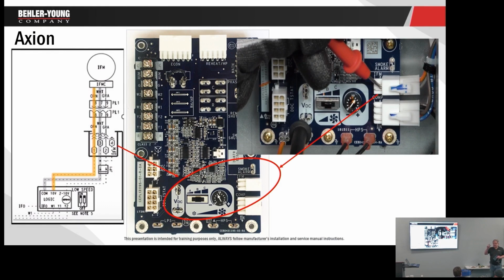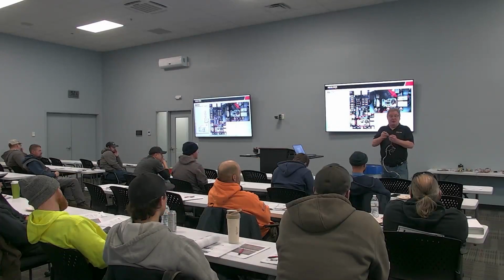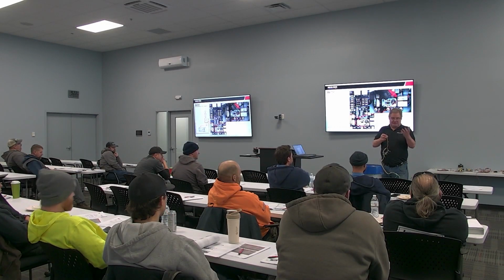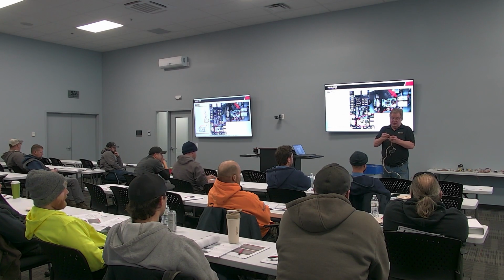The motor takes 230 or 460 and it creates 10 volts DC. In the electronics in the motor, it creates 10 volts DC that it sends back to this board. So remember when we turned this little dial here? We're adjusting that 10 volts DC. So up this orange wire, at the other end here, we've got orange, gray, and white. White is negative. Think of it as common, like you would with AC volts. So orange is 10 volts coming from this motor back to my board.